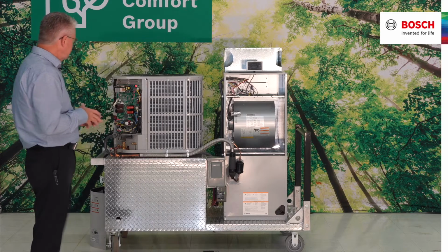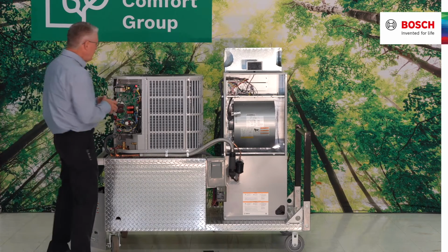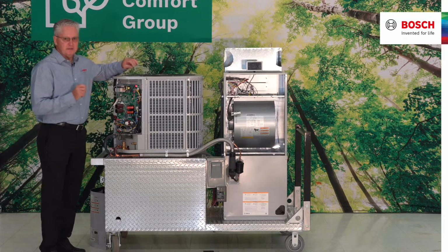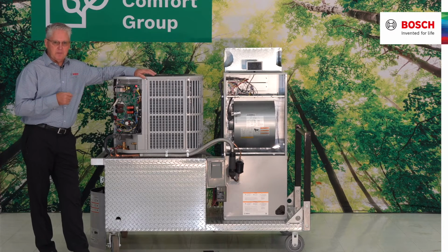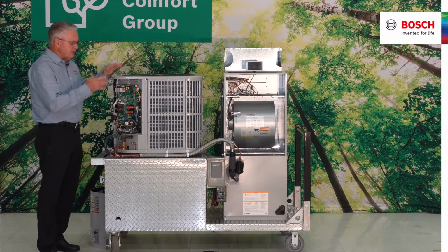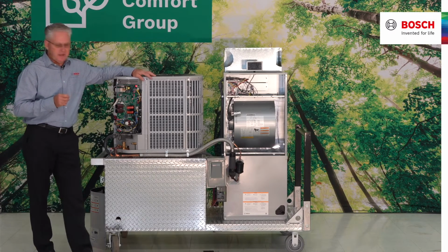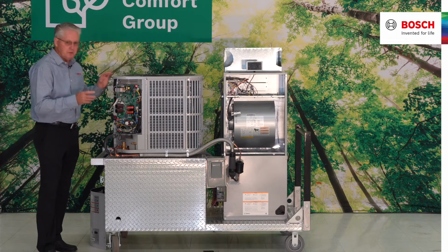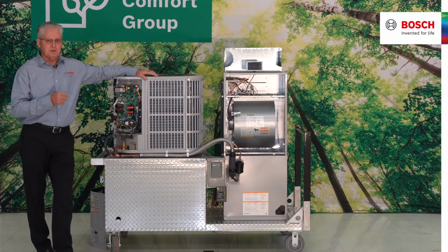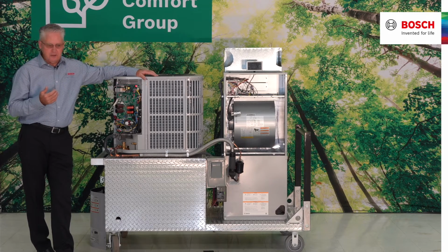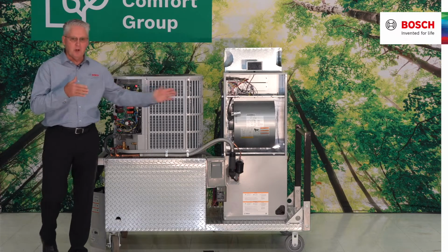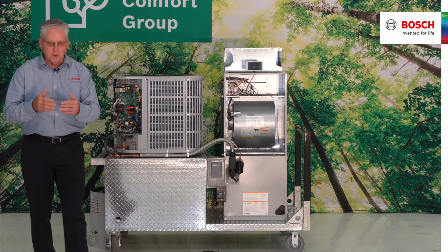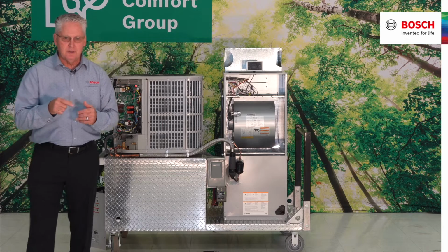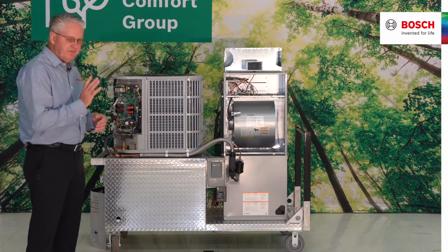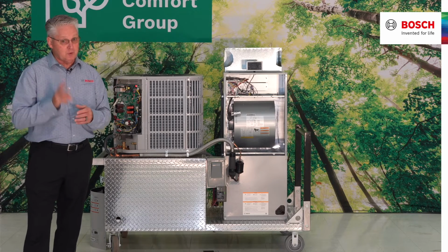So here's the thing. I've got a 15 Seer piece of equipment with a variable compressor. It uses the same technology as the 20 Seer. It uses the same technology to get that low amp draw when it first starts out. It uses the same technology to load match what's going on inside the structure. So I only still have to run 4 wires out there for a heat pump, 2 wires if it's just an air conditioner.